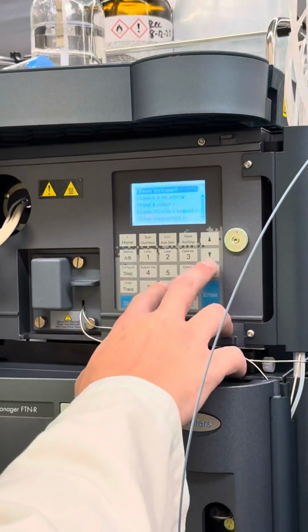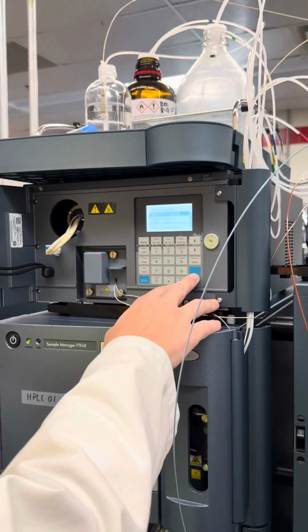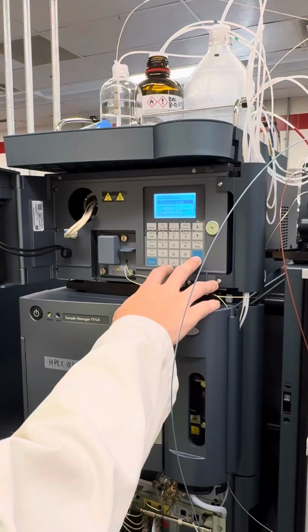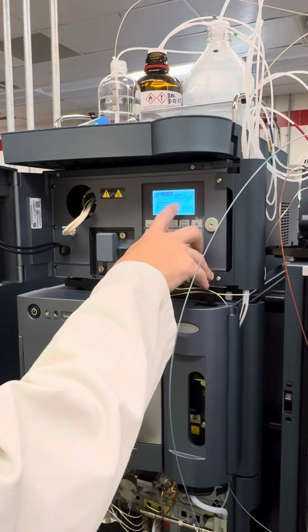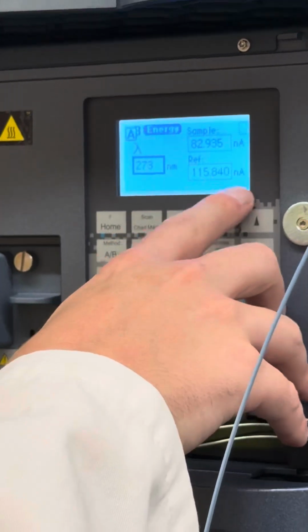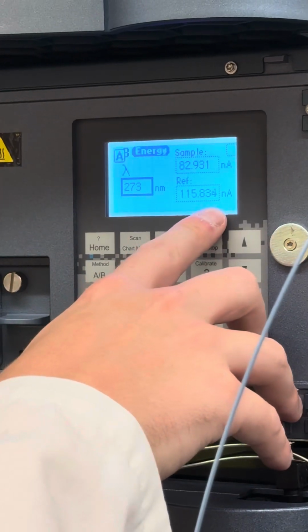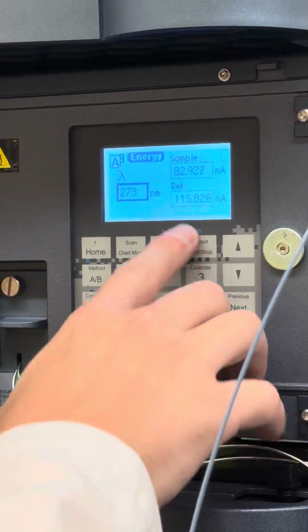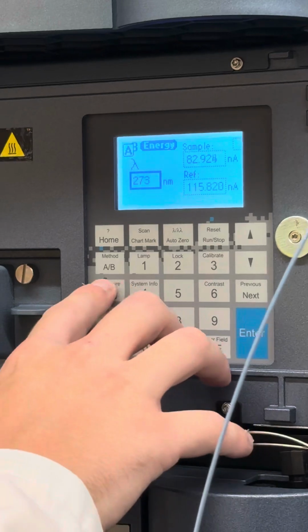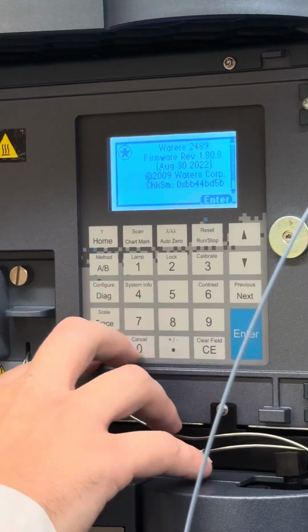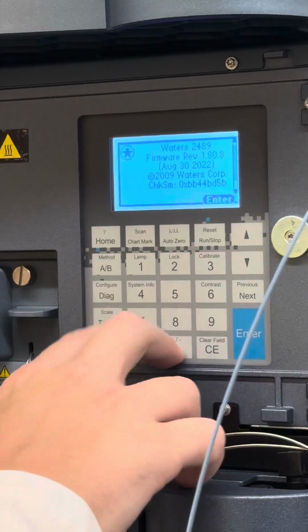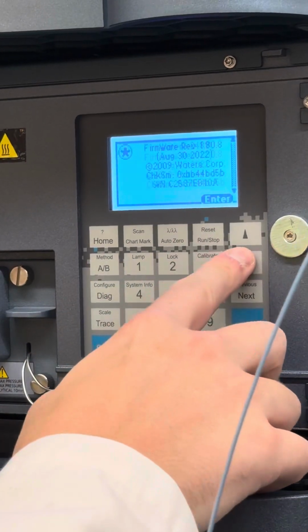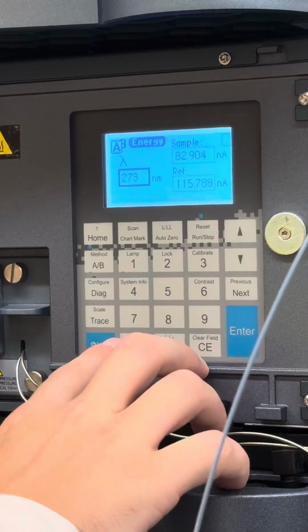We can look at the diagnostics tab. The sample and reference energy is going to be your big one here. You want to see that. You want to see your sample energy at about 70% of your reference energy here. So that looks really good. You can check your system info. If you hit shift, you can do all the ones on top. So there we go.